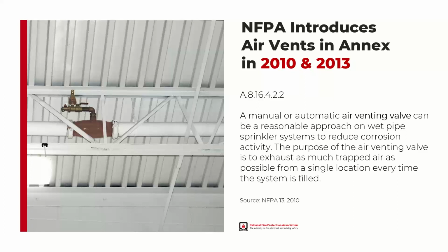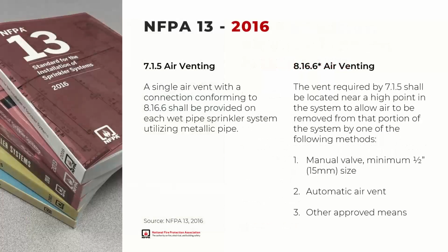So really in 2010 and 13 was the first mention in code that all wet systems should have some accommodation to get the trapped air out of the system. And then as that language grew, a committee was put together, and they suggested taking the should language and making it shall.